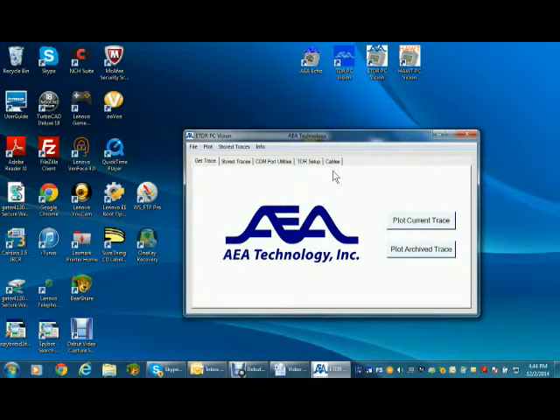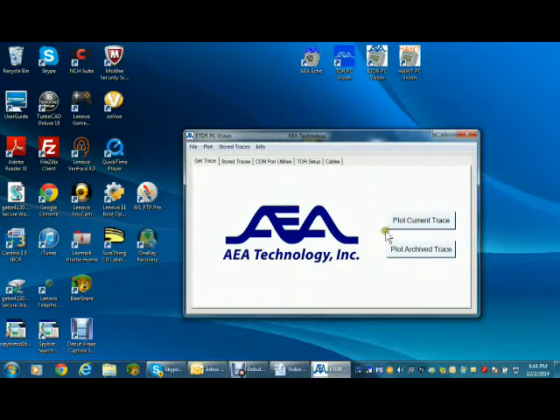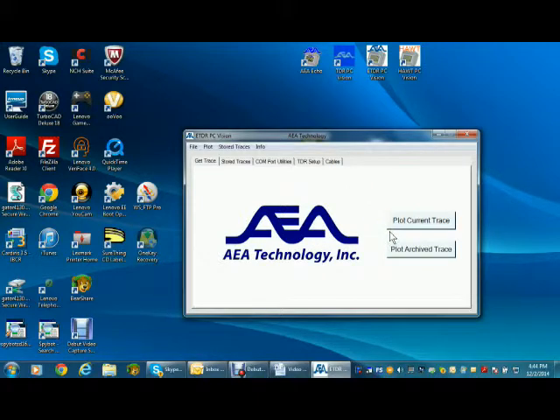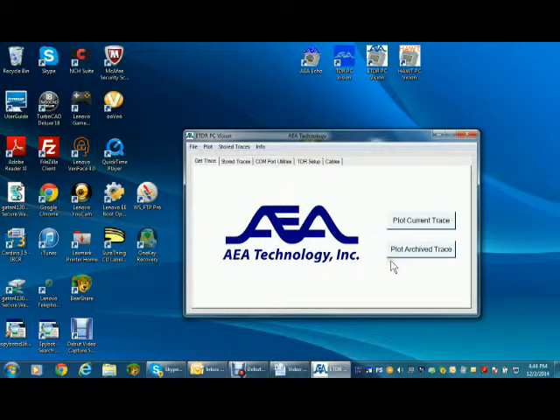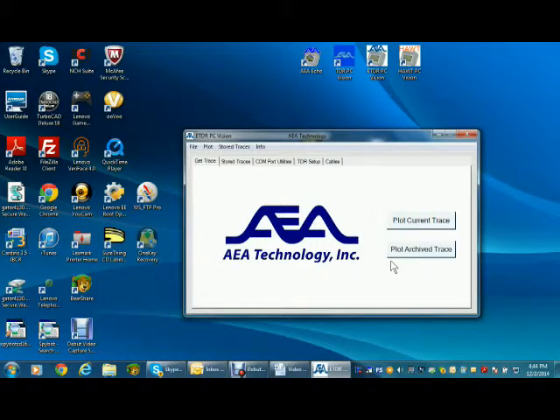In the Get Trace tab, you can press the Plot Current Trace button to upload a snapshot of live traces on the measurement screen, or press Plot Archive Trace to open a previously stored trace on the PC. The latter is always available even if no TDR is connected. This could be handy for emailing a trace to a supervisor or another technician who does not have a TDR connected to get a second opinion about the cable's condition.